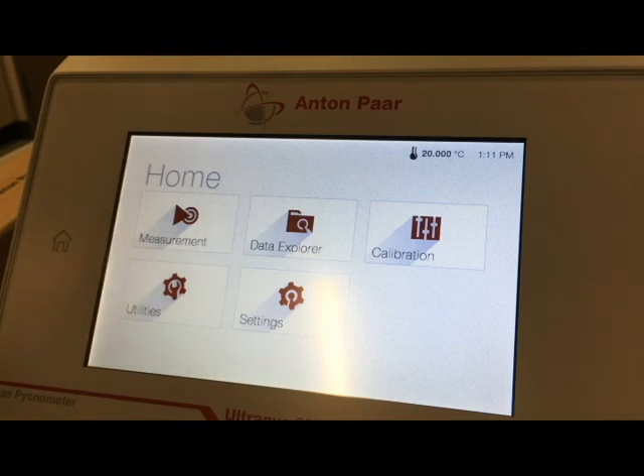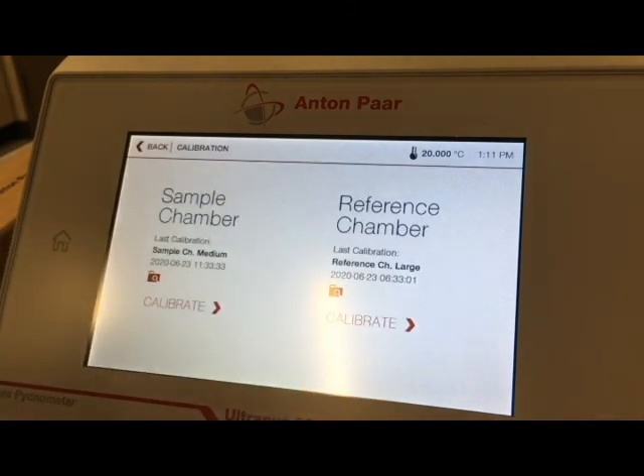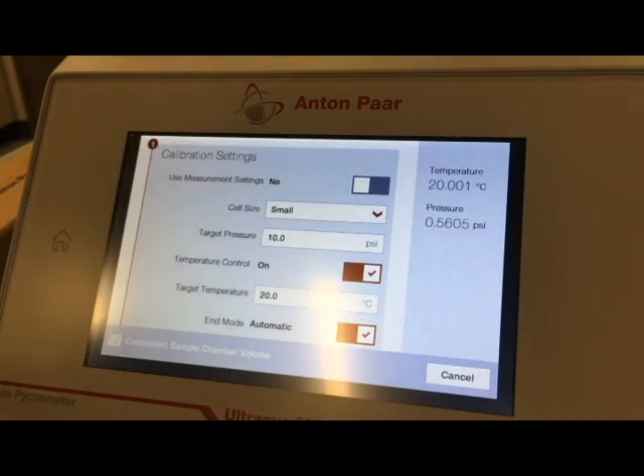At the start of each session of using the Ultrapyc 5000, or any time you change the settings significantly, such as the temperature, pressure, or size of the cell that you're using, you want to recalibrate the instrument to make sure that it's using the proper parameters. We'll do that by making sure you're on the home screen by pressing the home button on the left side here. And press calibration, and we're going to calibrate the sample chamber.